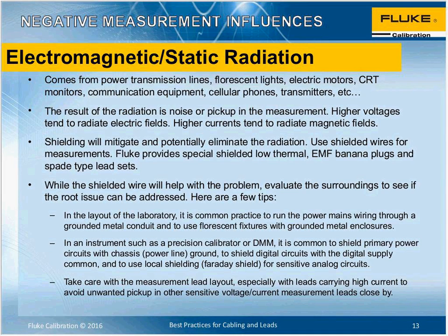And of course, as Rich has said a number of times already, the use of shielded leads is an obvious thing that we can do to provide some immunity, and also to prevent radiation, if we happen to have a lead set up where we might actually radiate some magnetic fields or electric fields from the measurements we're making. So as a company involved in these kinds of precision measurements, we do, as Fluke, provide some appropriate leads which look to improve the shielding, and also some of the other effects like thermal EMF and so on, with both banana plugs and some of those spade type leads, which you'll see will be more appropriate in different kinds of situations. So as I said right at the beginning, while the shielded wire will help with the problem, there are certain things that you can do to just be aware and be careful of.